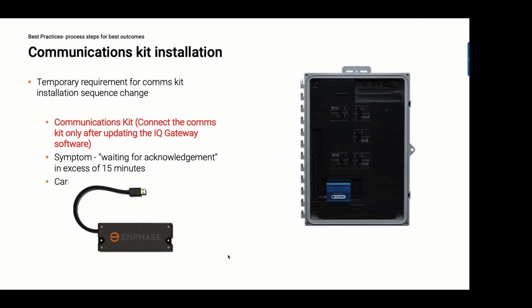All right, next best practice. This has to do with your communications kit. As most of you know, the communications kit is a wireless communications kit that gets plugged into the Envoy, and this communications kit is the device that communicates with the IQ batteries as well as the IQ System Controller. We do this wirelessly, and so this is the wireless comms kit. What we have is a little situation with the comms kit getting plugged in, and when we're updating the software, it could potentially render the comms kit non-functional, and that has to do with a software load.